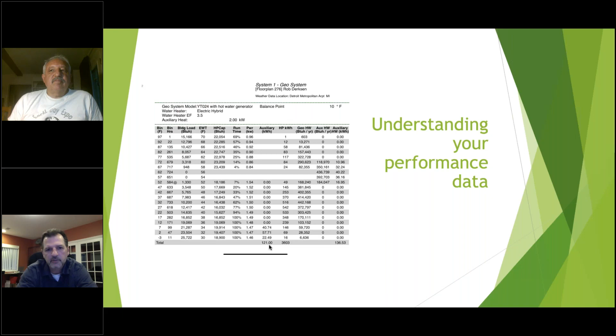You can see in this center column, the auxiliary heat in this application is 121 kilowatt hours per year. That, at the going rate of electricity, is somewhere around $15 worth of energy. So to increase the equipment size, the ducting size, and the geothermal loop size would provide no value in reasonable recovery in energy cost or energy production for that matter. So utilizing software that provides us with kilowatt hour estimates based on the weather for the area is very important.